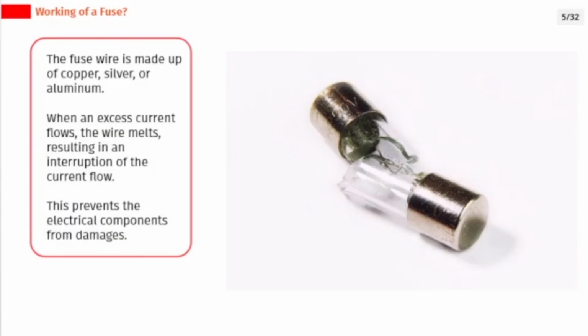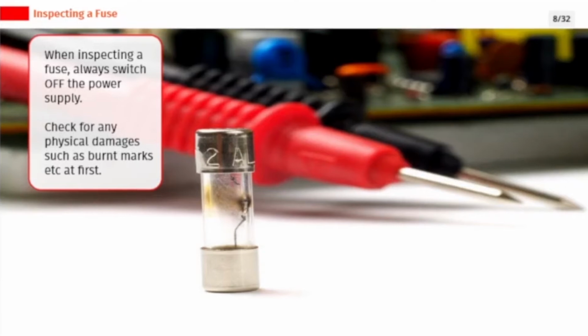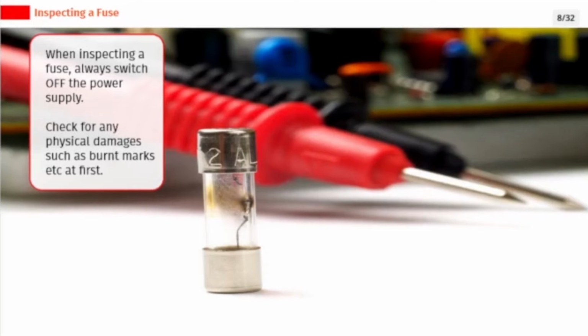The fuse wire is made up of copper, silver, or aluminum. When an excess current flows, the wire melts, resulting in an interruption of the current flow. This prevents the electrical components from damages. When inspecting a fuse, always switch off the power supply. Check for any physical damages such as burnt marks etc. at first.